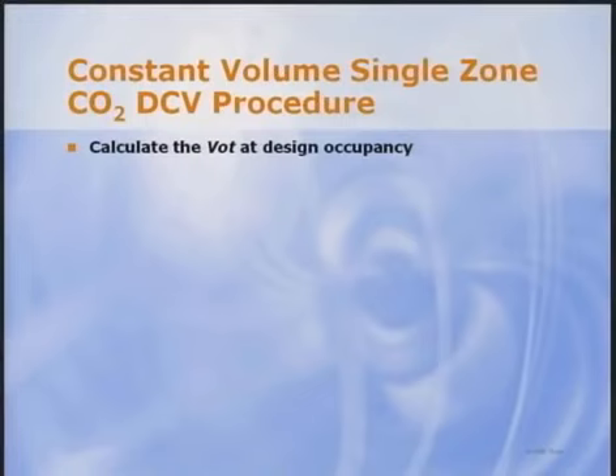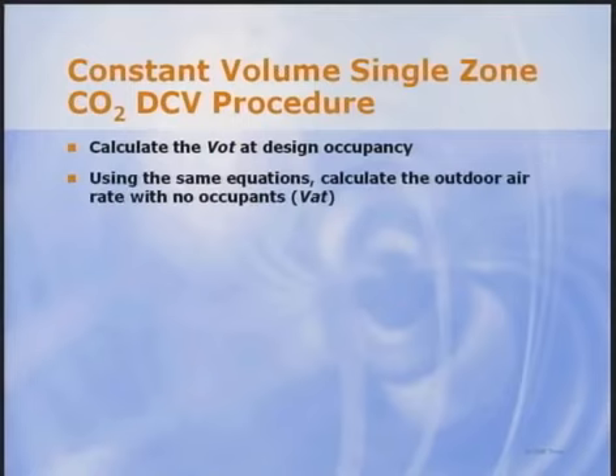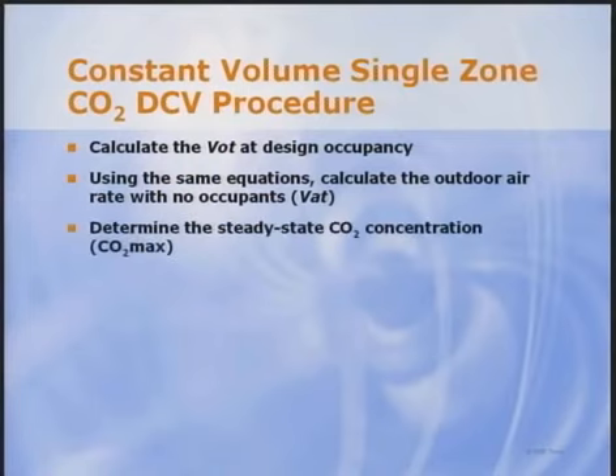The user's manual outlines a step-by-step procedure for CO2-based DCV. First, calculate the design outdoor air rate, assuming all occupants are present, per the Standard 62.1 equations that Dennis discussed. Next, use the same equation, but assume 0 occupants. Call this value VAT, or the total ventilation rate based on the area component only. Then, calculate the steady-state CO2 concentration using the equation on the previous slide. Call this value CO2 max.